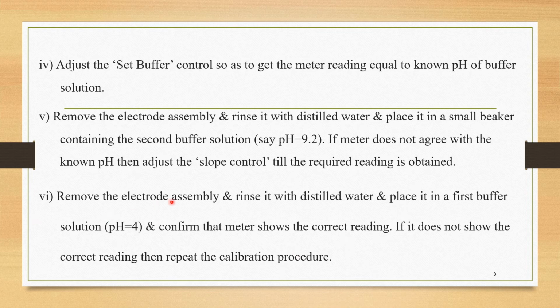The next step, what we have to do? We have to again remove the electrode assembly from the pH equal to 9.2 buffer solution. Then again we have to rinse it with distilled water and reinsert it in the first buffer solution of pH equal to 4, and check whether the meter reading is equal to pH 4. If it does not show the correct reading, then repeat the calibration procedure. In some cases, if it cannot give the correct pH of 4, we again have to repeat the calibration procedure.